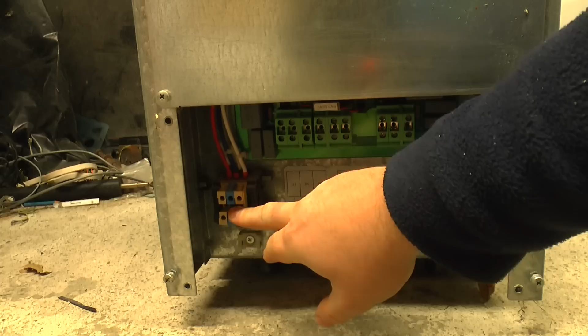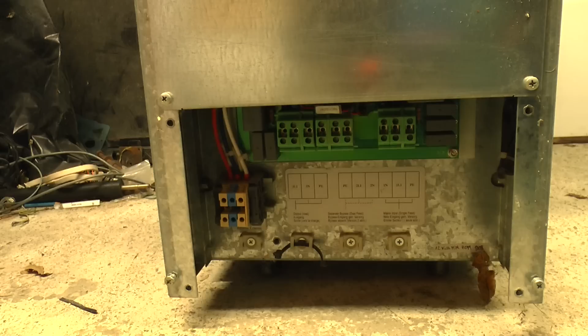So this is providing the supply for running the UPS itself. The load will come directly off the mains, and if there's a mains failure, it'll switch in. Basically like a standard line interactive UPS. If you're using just these ones instead, then it's a purely online UPS. Interestingly, the maintenance bypass is actually single pole. It switches in this one.